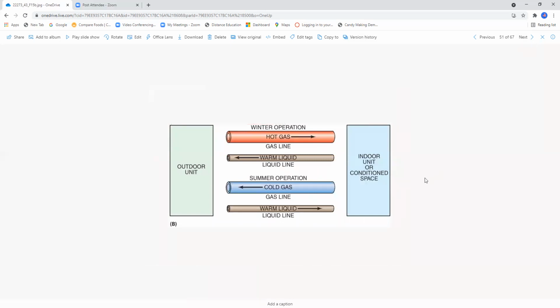Okay, this shows what happens with the refrigerant in winter and summer. In the winter, you have hot gas going through the large suction line, and warm liquid, not hot liquid, going through the liquid line to the outdoor unit. In the summer, we have cold gas going through the suction line back to the compressor, and we have warm liquid leaving the outdoor condensing unit coil, going to the metering device. Remember, on heat pumps, you usually have 2 metering devices, one for heating, one for cooling.